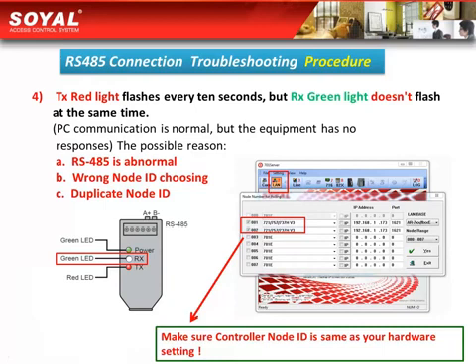Fourth, check whether the TX red light flashes every 10 seconds. If the TX red light flashes every 10 seconds but the Rx green light does not flash at the same time, it means the PC communication is normal but the equipment has no response. The possible reasons are: first, the RS485 cable is abnormal; second, the wrong node ID is chosen; or third, there is a duplicate node ID.